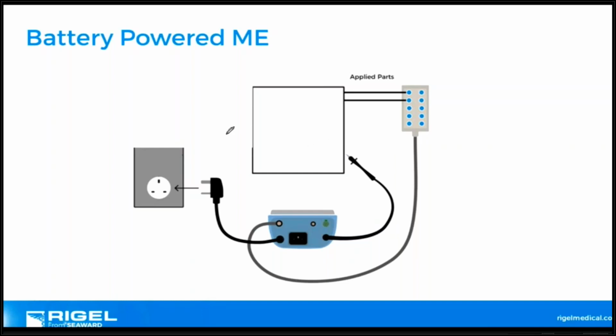60601, you go from chassis to chassis. But if you have this in your hands, and this is the medical device, it's pretty much common sense. You're looking at areas of potential. Let's say this is an accessible conductive part. You just want to make sure that from any conductive parts to the applied part, there's no hazardous current. So that's what we're measuring.